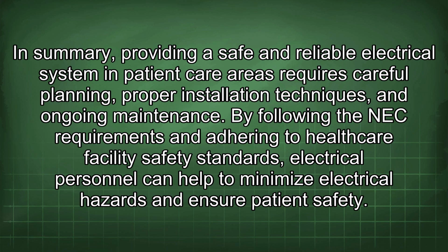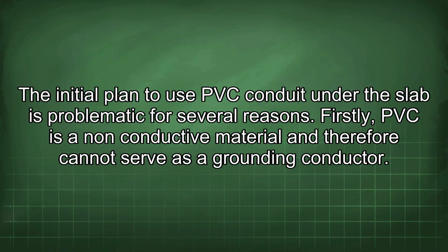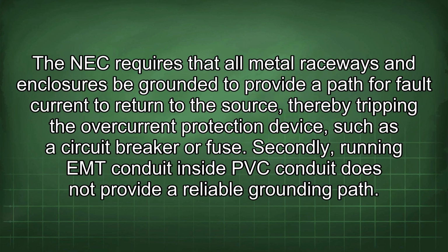The initial plan to use PVC conduit under the slab is problematic for several reasons. Firstly, PVC is a non-conductive material and therefore cannot serve as a grounding conductor. The NEC requires that all metal raceways and enclosures be grounded to provide a path for fault current to return to the source, thereby tripping the overcurrent protection device such as a circuit breaker or fuse.